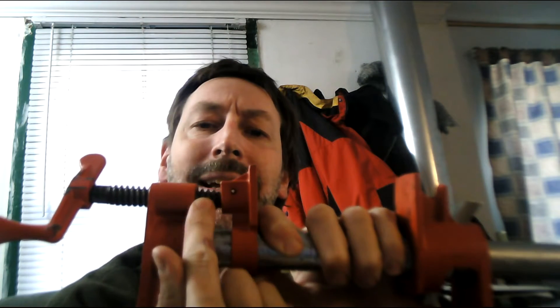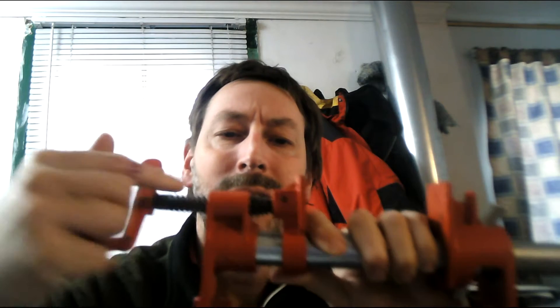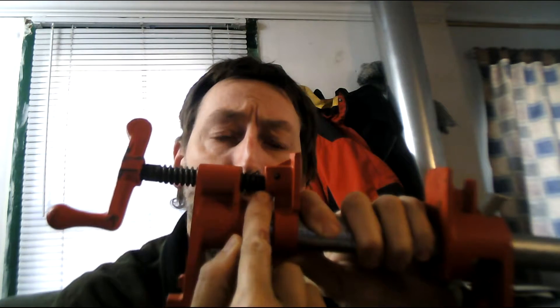The other thing I want to draw your attention to is the little bit of thread here. Bearings aren't that tall, so you count 1, 2, 3, 4 threads. That means that turning the handle four times — 1, 2, 3, 4 — is all you need to do in order to seat the bearing. How you're going to know it's reached its home is that it won't turn anymore. It'll get really hard to turn and you'll reach the maximum point.